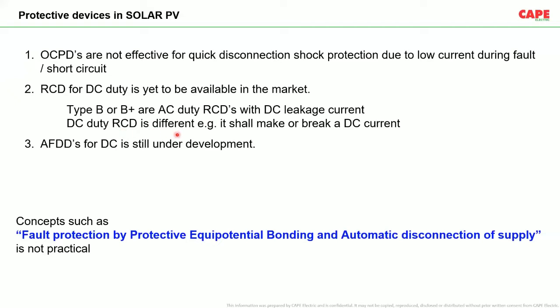A DC duty RCD is a little bit different from an AC duty RCD, because in DC the making and breaking shall happen on DC current, and breaking a DC current is different from making and breaking an AC current. I have been trying to find a DC duty RCD, and I could not find one in the market. The standards are already in place. In 2017, an IEC standard was published for DC duty RCD, with a lot of additional testing. But so far, I think that kind of product is not available in the market.